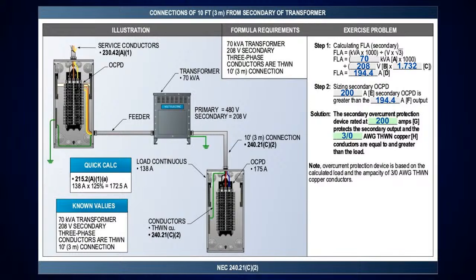Now, this particular one, we're looking at (C)(2), and this is connections for 10 foot here. So when you look at this, all you're going to do is treat it just like we do a transformer calculation. You remember I did a presentation on here where I showed how to calculate transformers. This is the same thing for sizing your conductors. All you needed to know was the kVA of the transformer, multiply it by 1,000, put it in VA. Then you take the voltage. In this case, it's a 208 volt three phase, so I multiply the 208 volts times 1.732, which is going to give me 360, and I divide that into the VA of the transformer, which gives me 194.4 amps.